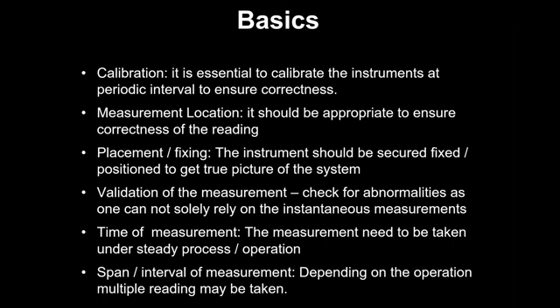The next is validation of the measurement. All said and done, we are doing measurement for a certain period of time, and it is quite possible that the measurement can be erroneous if the values are abnormal. If everything is in the normal range, you get a normal pump efficiency, cooling tower performance normal, chiller normal, then you don't doubt so much. But if there is an abnormality, if you see that suddenly the pump is giving just 20% of the flow rate, or somewhere you see that a temperature is way higher than what it should be, then it could be possible that there is an issue with the measurement.